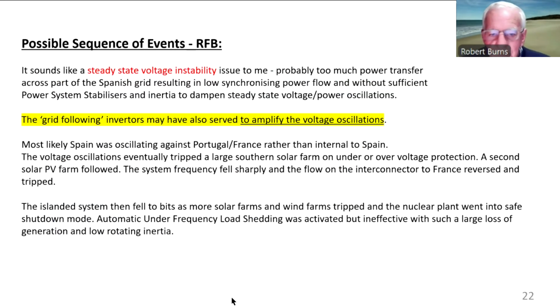Now, if I put my system operator hat on, this is very similar to what I've seen before. It's a steady state voltage instability. This can happen when you have too much power flowing across the grid with too low synchronizing power flow and inadequate damping of the steady state voltage or power oscillations. The grid following inverters, in fact, may have served to amplify the voltage oscillations. The grid following circuitry has a thing called a phase locked loop, and it basically just mimics the supply voltage. So if the supply voltage is not a sine wave, but has little ripples on it, it will do the same thing. It'll follow those ripples. And if you've got 20,000 megawatts coming out supporting those ripples, well, guess what? It supports and amplifies those voltage oscillations.